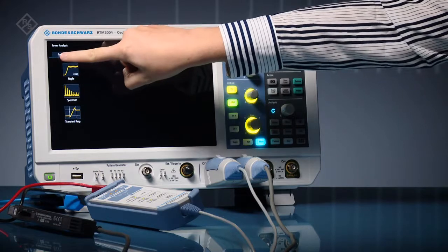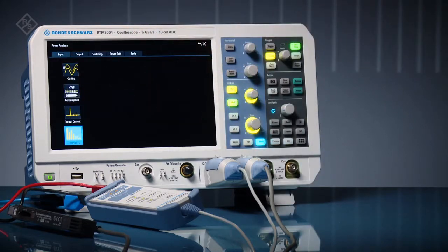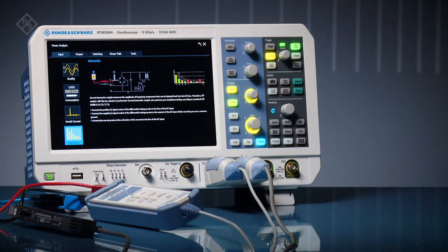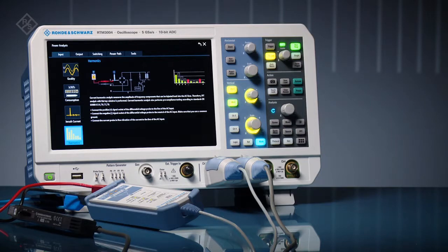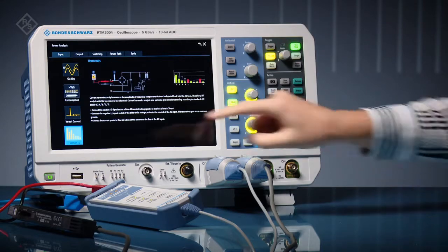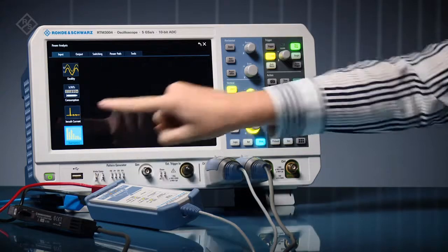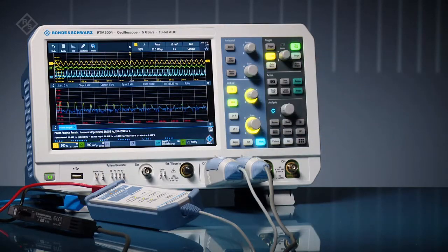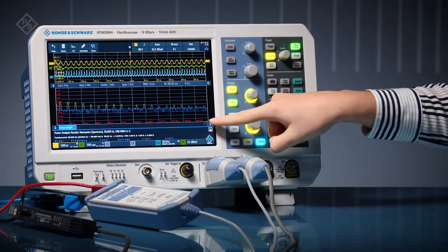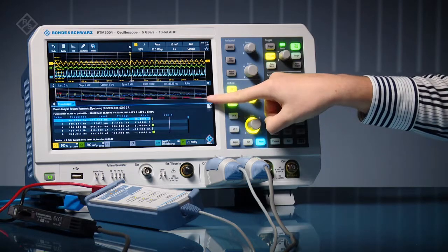In this example, we'll determine pre-compliance for harmonics. The application shows where to connect your high voltage differential probe and your current probe. The application also automates measurements. Simply look at the results, such as this harmonic analysis.